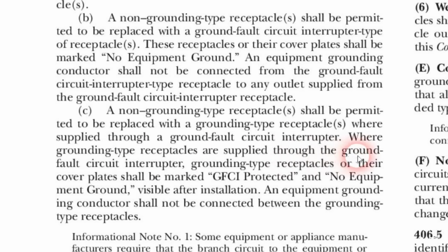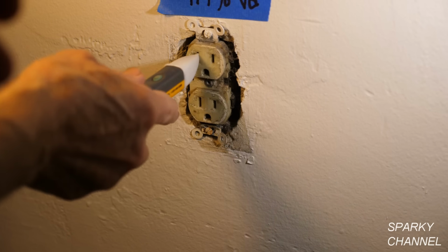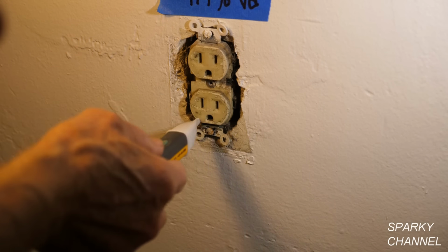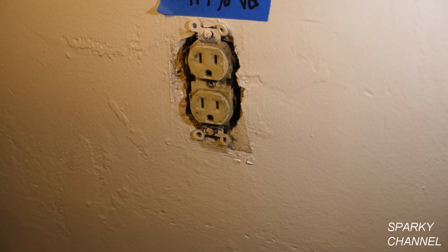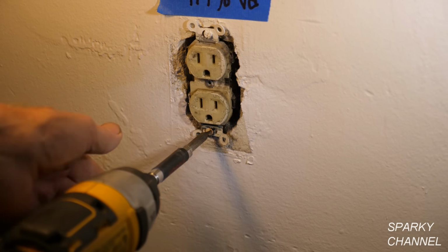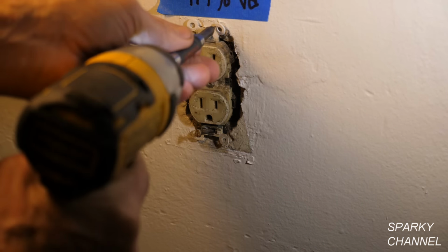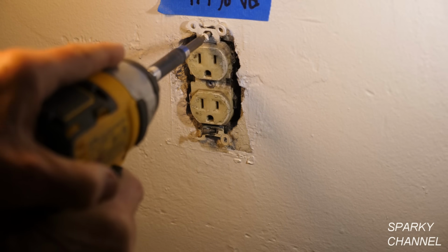The first thing we're going to do is turn off the circuit breaker. Next, I'll do a double check with my Fluke voltage sensor. The voltage sensor agrees with the receptacle tester that the electricity is off. So now the task is to remove all 7 of the old receptacles on the circuit. My technique now is to spin the terminal screws off with my impact driver, which leaves the copper wires undisturbed while removing the outlet. Now I vacuum out the old box, which after 60 years can be quite dusty.